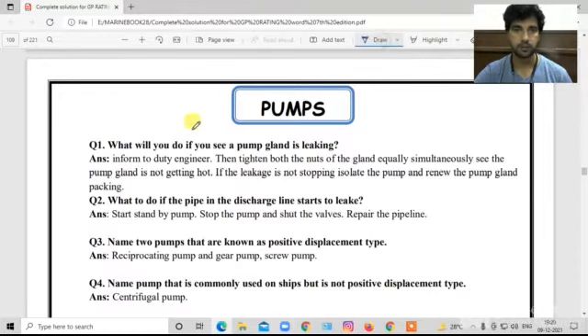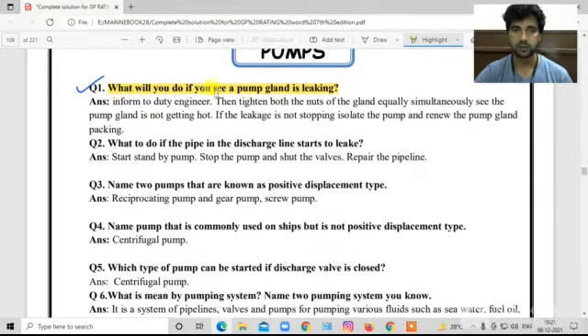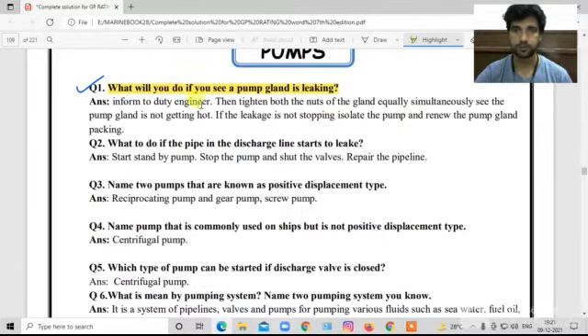Question number one: What will you do if you see the pump gland is leaking? If the pump gland packing is leaking, first we will tell the duty engineer. Then tighten both nuts of the gland equally and simultaneously. Check that the pump gland is not getting hot. If the leakage is not stopped, then we will renew it.